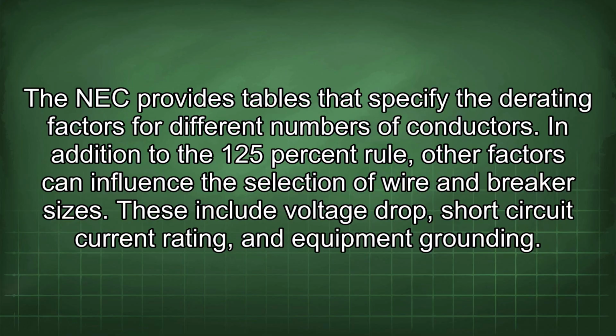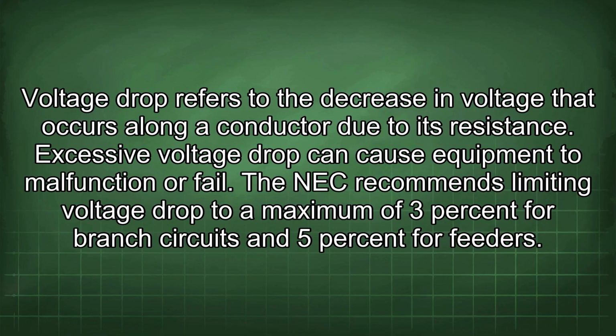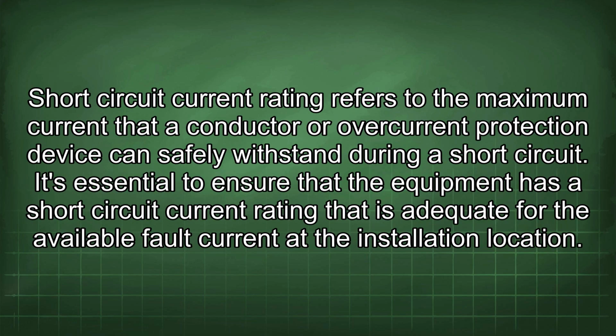In addition to the 125% rule, other factors can influence the selection of wire and breaker sizes. These include voltage drop, short circuit current rating, and equipment grounding. Voltage drop refers to the decrease in voltage that occurs along a conductor due to its resistance. Excessive voltage drop can cause equipment to malfunction or fail. The NEC recommends limiting voltage drop to a maximum of 3% for branch circuits and 5% for feeders. Short circuit current rating refers to the maximum current that a conductor or overcurrent protection device can safely withstand during a short circuit. It's essential to ensure that the equipment has a short circuit current rating that is adequate for the available fault current at the installation location.